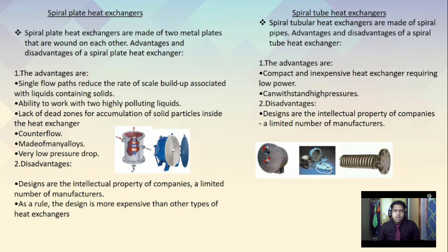The advantages and the disadvantage are, first, single flow path reduces the rate of scale build up associated with liquid containing solids. Second, ability to work with two highly polluting liquids. Third, lack of dead zone for accumulation of solid particles inside the heat exchanger.